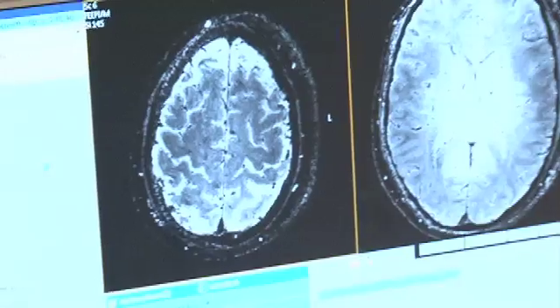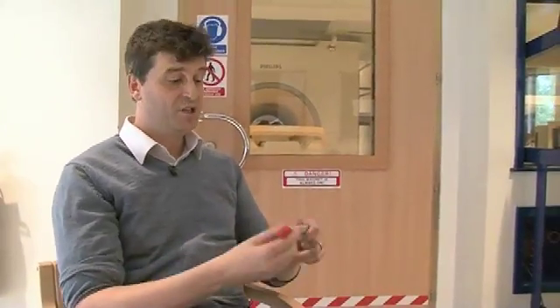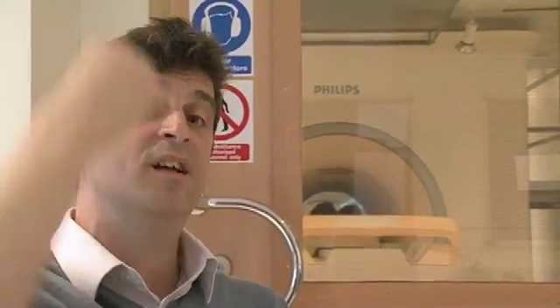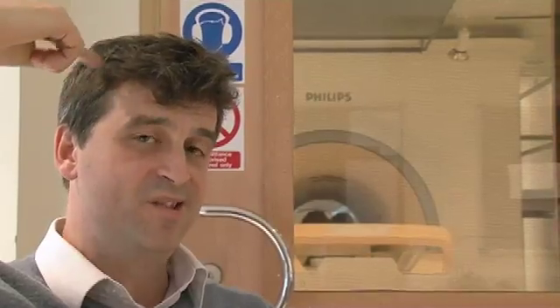The way we excite the nuclei and make them precess is by firing a pulse of radio waves into Martin's brain. We then get back from the nuclear magnets a kind of echo of radio waves produced by that precession of the net nuclear magnetization. To make a picture, we make the magnetic field slightly different in different places in the person's body. The frequency of precession then differs by location — for example, a high field at the top of the head produces a high frequency signal, and a low field at the bottom produces a low frequency signal. We can therefore assign each signal to a position.